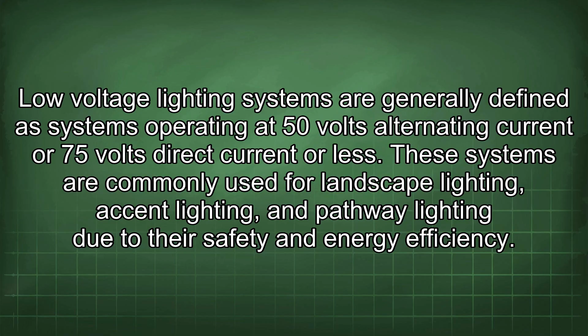Low-voltage lighting systems are generally defined as systems operating at 50 volts alternating current or 75 volts direct current or less. These systems are commonly used for landscape lighting, accent lighting, and pathway lighting due to their safety and energy efficiency. The installation of low-voltage lighting typically involves burying low-voltage cables, connecting fixtures to the cables, and connecting the system to a transformer that steps down the standard 120 volts alternating current to the lower voltage required by the lighting fixtures.